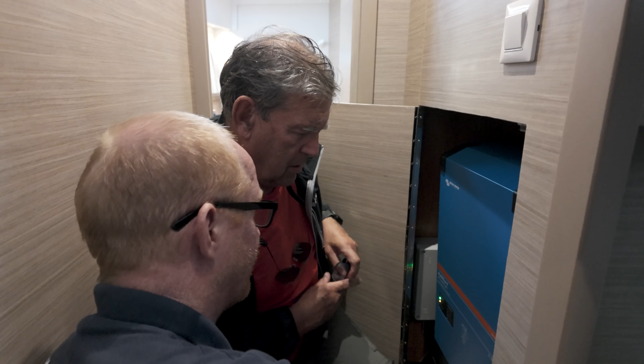So inside here, just so you're aware, you can see there's an RCD and an MCB. The MCB limits it, so you've got 10 kilowatts, so 63 amps. So if for any reason you're not getting power, this is where you come and look. So you can see I've got mains available and I'm in bulk charge at the moment, so it's charging the batteries.